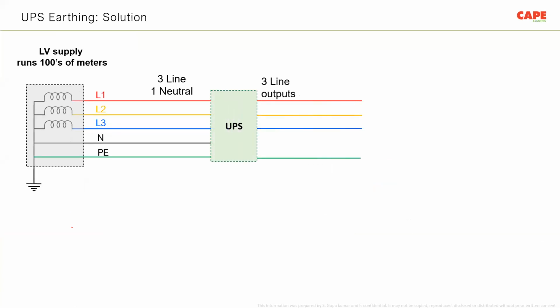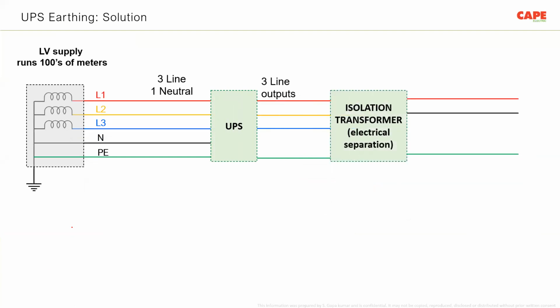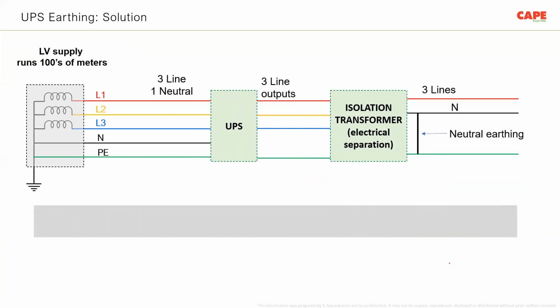Then what to do? You have a UPS. If the UPS has a 3-phase output, and you want to connect a single phase load, please use an isolation transformer, and the isolation transformer neutral must be earthed in this fashion where I am showing. You have the 3-phase output from the UPS, then you have an isolation transformer. So it is electrically separating the load circuit.